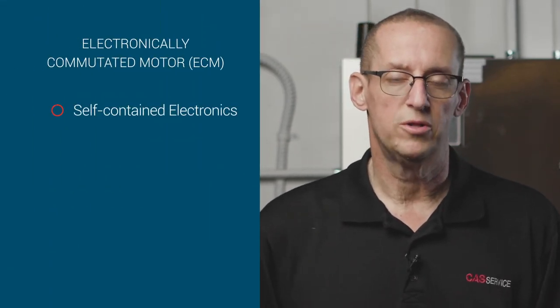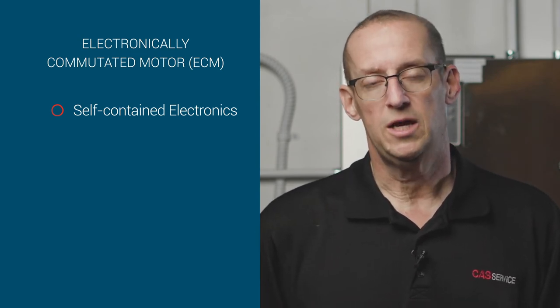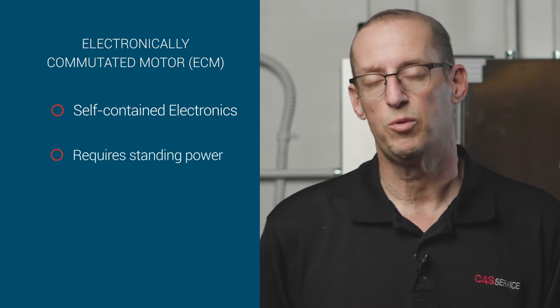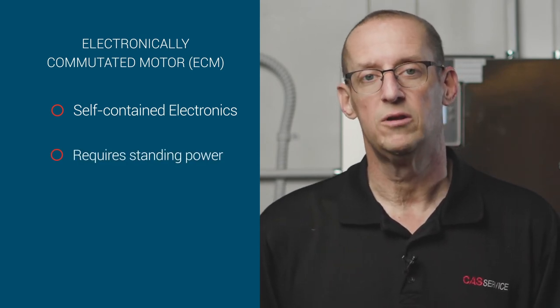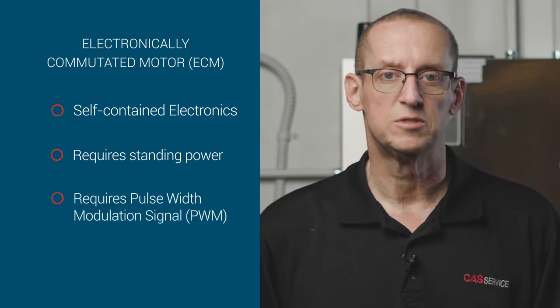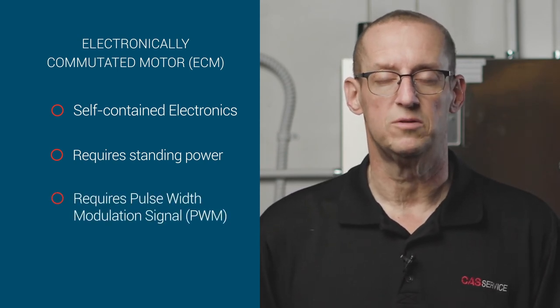The rest of our motor control involves a totally unique type of motor that we use here — it's an EC motor, an electronically commutated motor. All the electronics that motor needs to run are contained within the motor itself. That motor gets high voltage applied to it from the breaker panel as standing power, and then in order to get that motor to run, it has to receive a PWM signal, or a pulse width modulation signal. That can be generated in a couple of different ways.